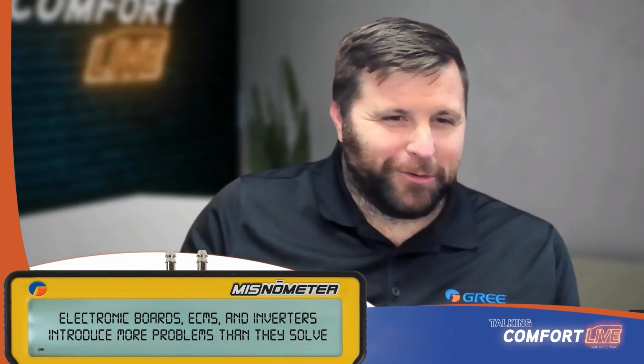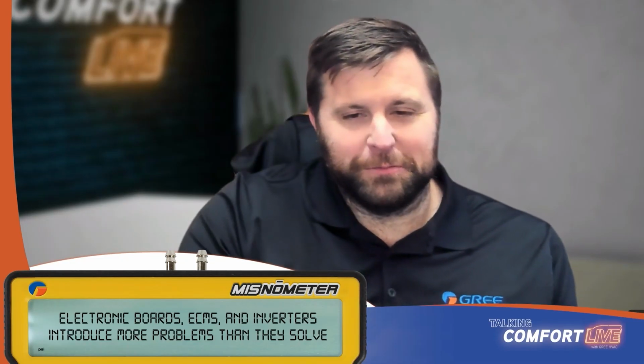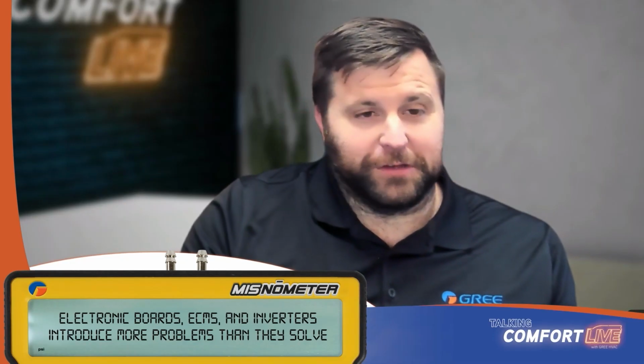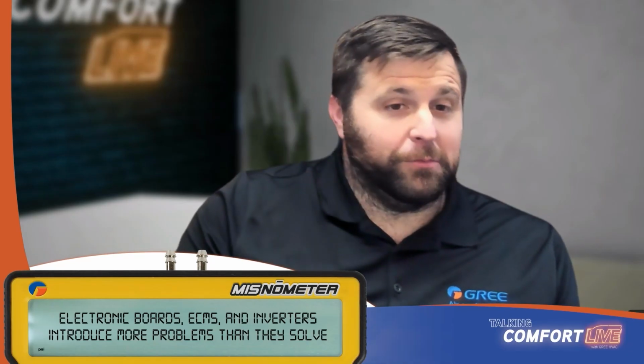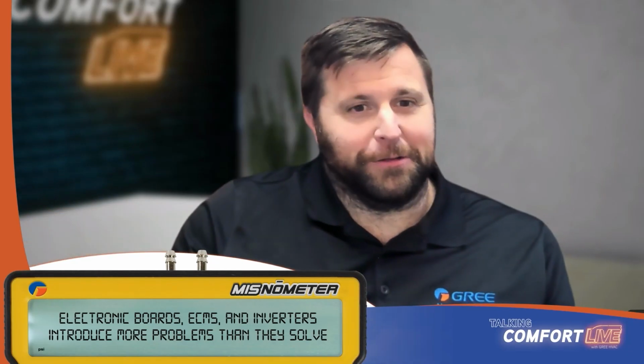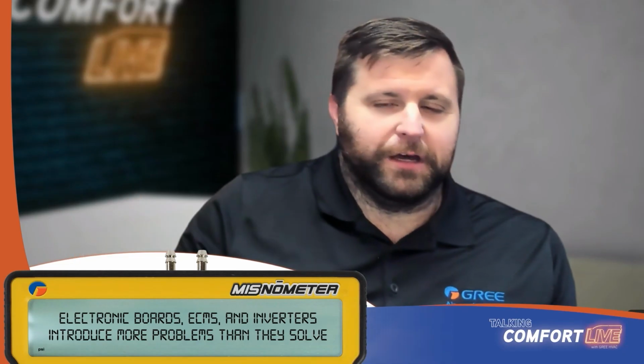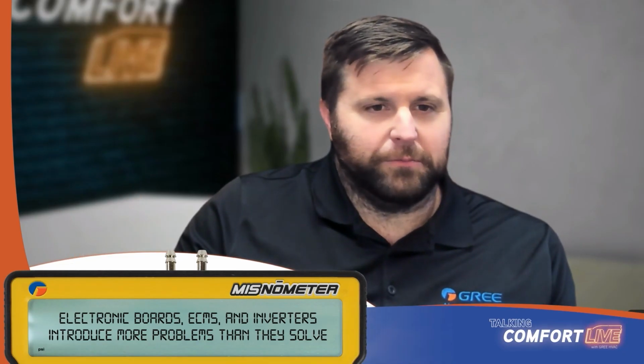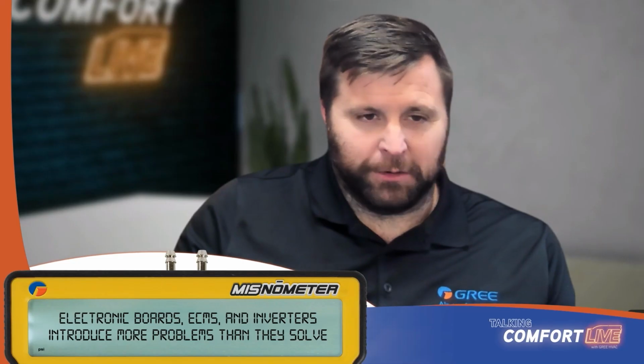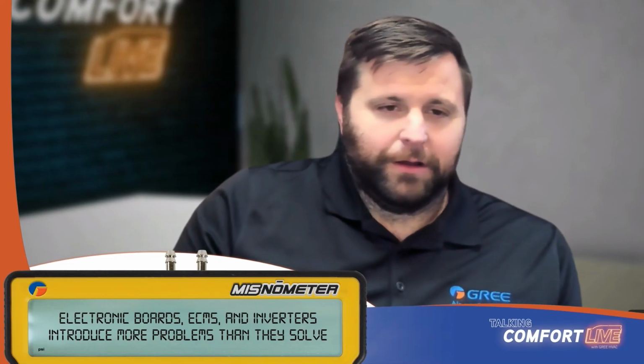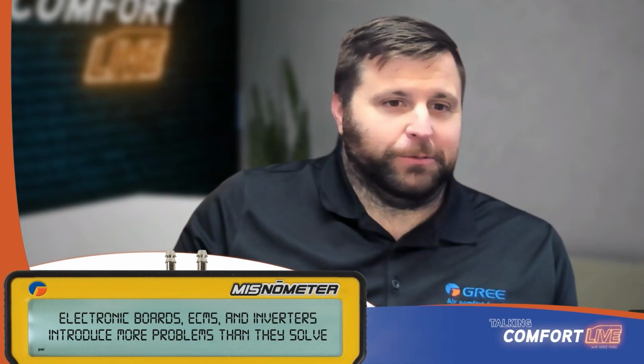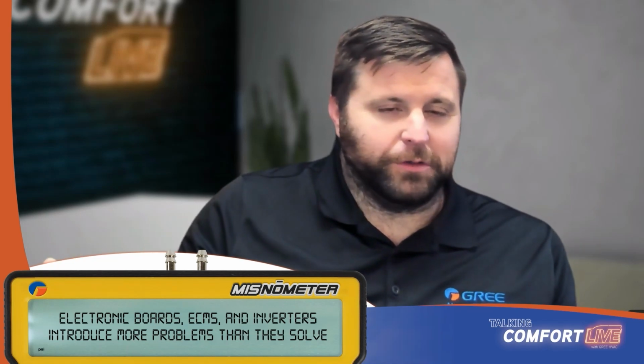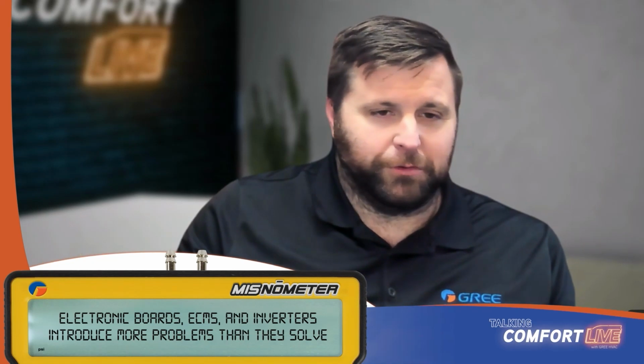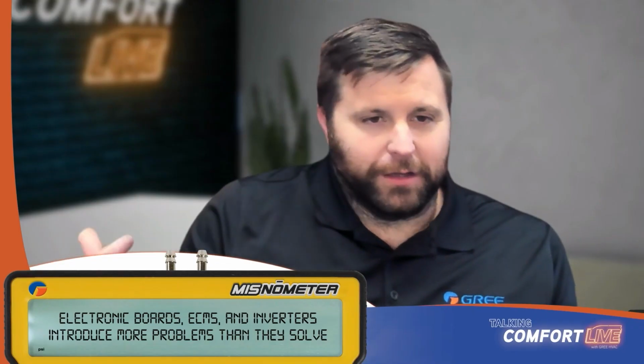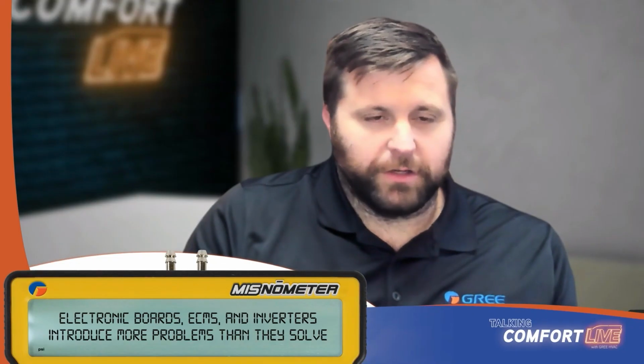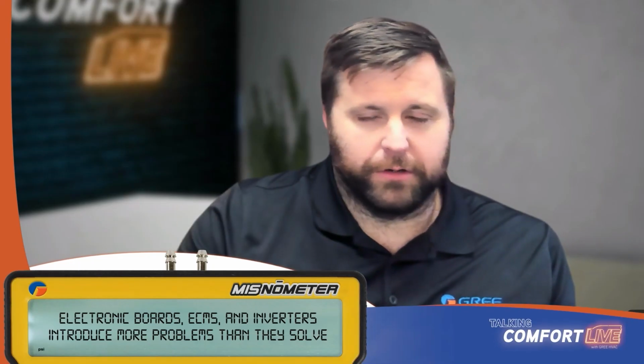If you've got poor airflow, it's something that people seem to find a lot during this time of year. For the folks up north, it's been a few months now, but the folks down south, who are maybe just now finding out, start getting error codes on mini splits when they go over to heating. It ran fine all summer. Well, airflow. The first thing I would check on a mini split like that is just walk over and take a look at the filters. Take a look at the blower wheel. It might be dirty, you might have poor airflow, and it trips out on an error code.